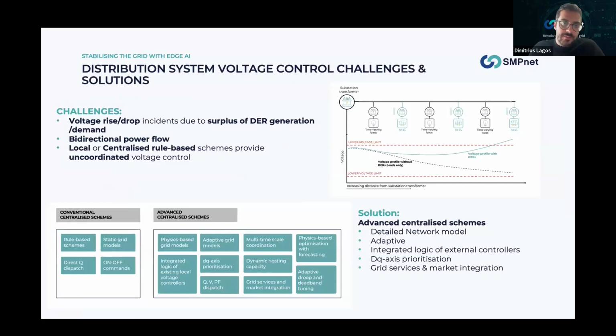So, of course, the distribution system comes with its own challenges regarding voltage control. As we have DERs and loads on a distribution feeder, we can have various voltage incidents. For example, voltage rise if we have a surplus of DER generation, or voltage drop if we have a surplus of demand, for example, if we have a lot of EVs charging on the network. And at the moment, the solutions to address these issues are mainly based on local or centralized rule-based approaches. That means that we have some static models and simplified rules with if-then-else logic that, according to these rules, activate specific resources in the grid to resolve the issues.